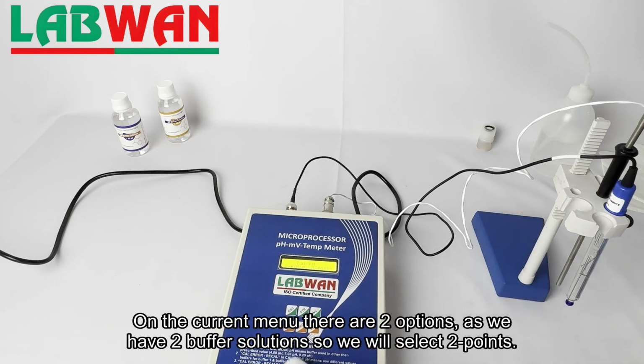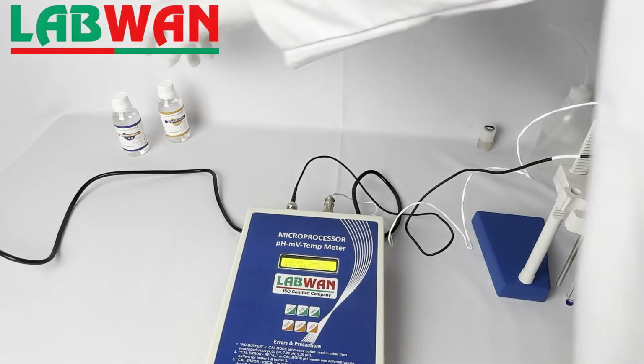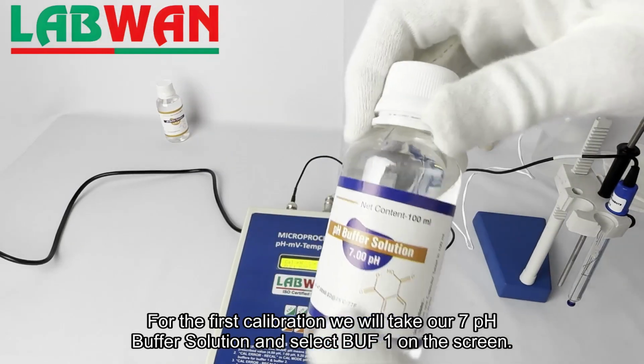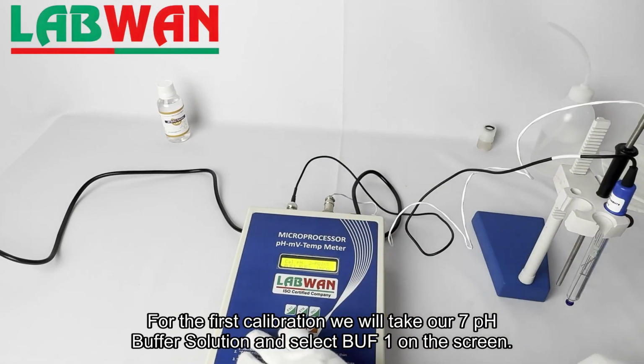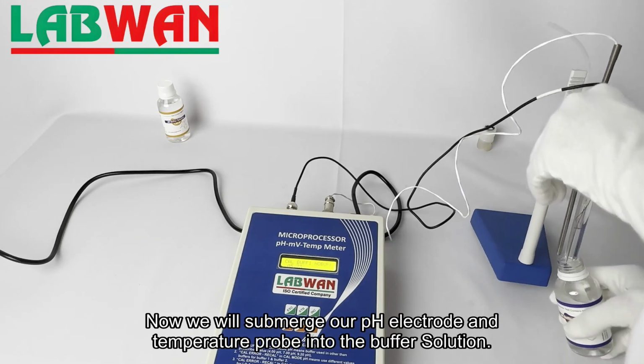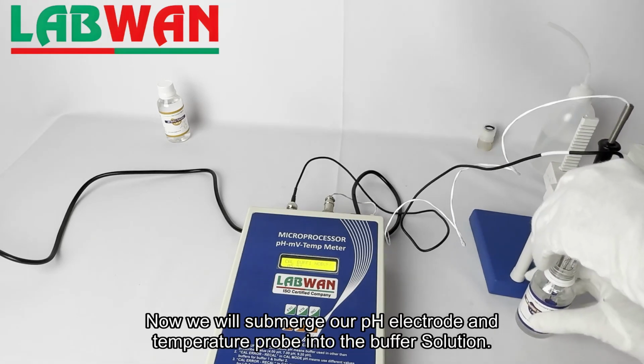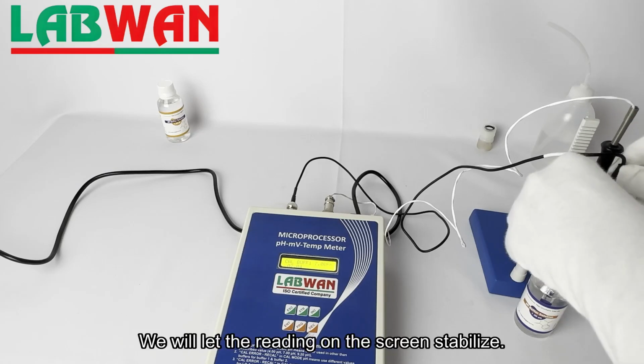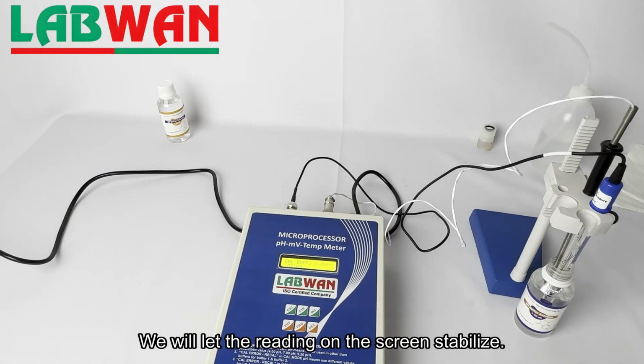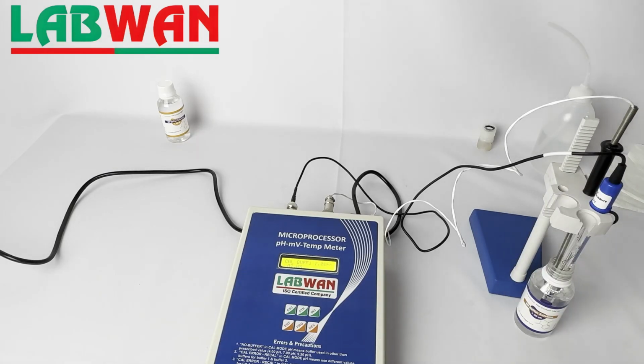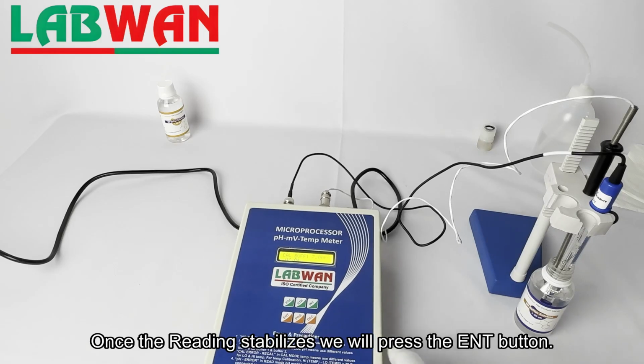On the current menu there are two options. As we have two buffer solutions so we will select 2 points. For the first calibration we will take our 7 pH buffer solution and select BUF1 on the screen. Now we will submerge our pH electrode and temperature probe into the buffer solution. We will let the reading on the screen stabilize. Once the reading stabilizes we will press the ENT button.